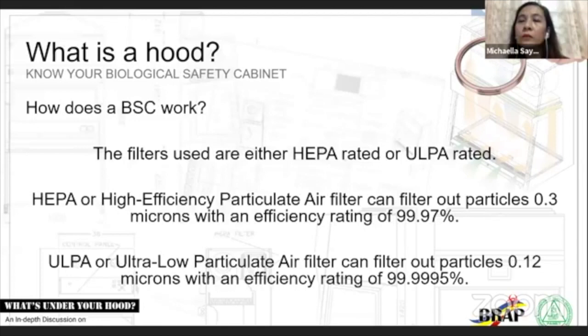Now, ULPA filters, or your ultra-low particulate air filters, can filter out particles 0.1 microns in diameter with an efficiency rating of 99.9995%. So I guess everyone will be shifting to ULPA filters now. But before you do that, you need to, again, go back to your work processes and determine what you actually need, because definitely ULPA filters would cost more than your HEPA filters.